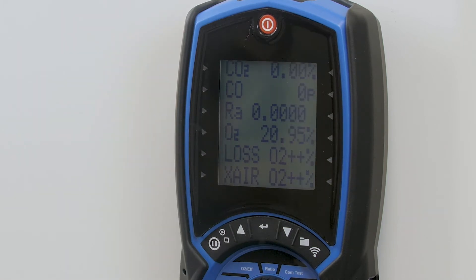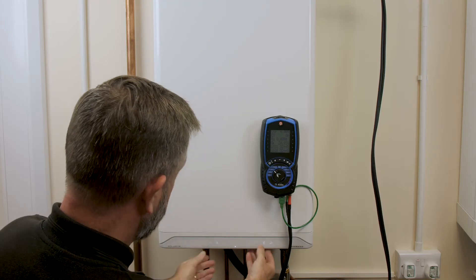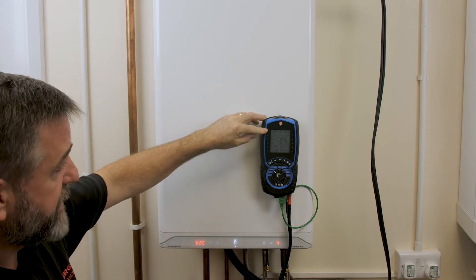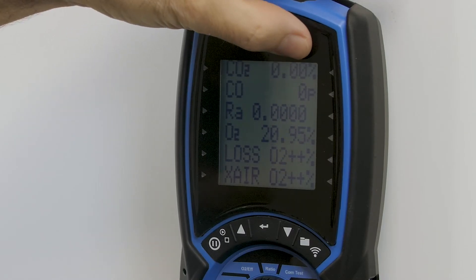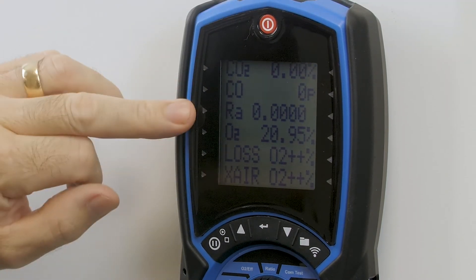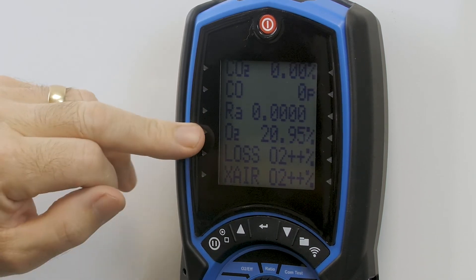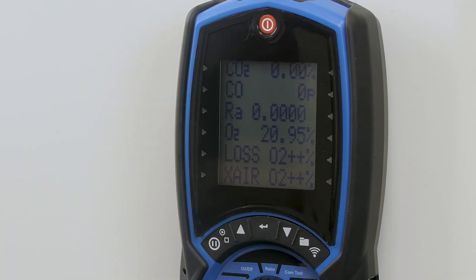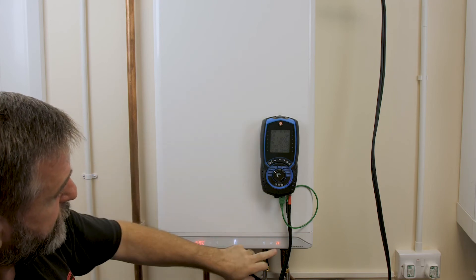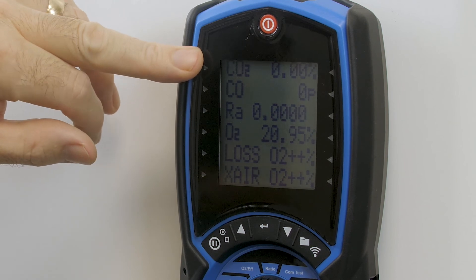I'll put the boiler now into engineer mode on high fire. If flue integrity is good, we should maintain zeros on CO2 and CO. Your ratio should ideally be 0.0000 and your O2 at approximately 20.9. With the boiler on high fire, we can confirm that our flue integrity is sound.